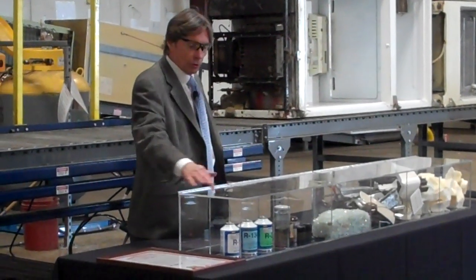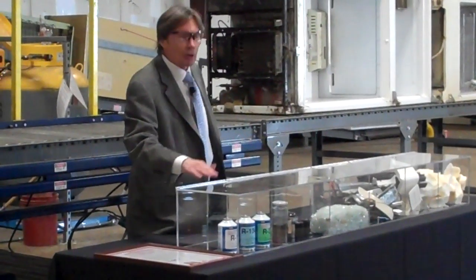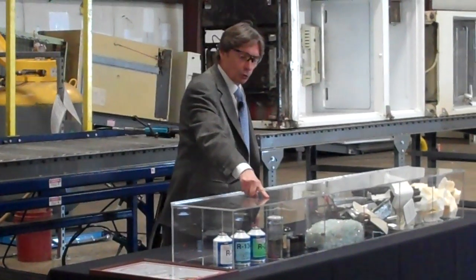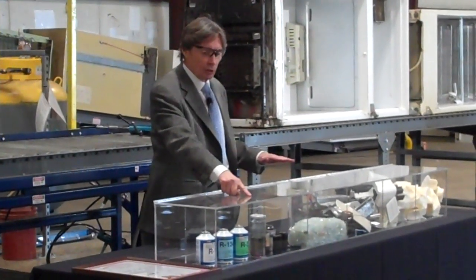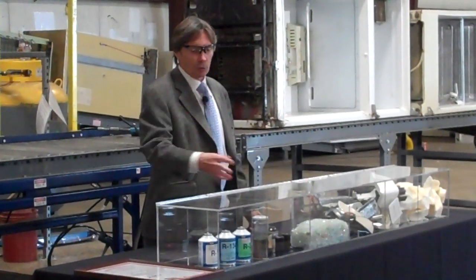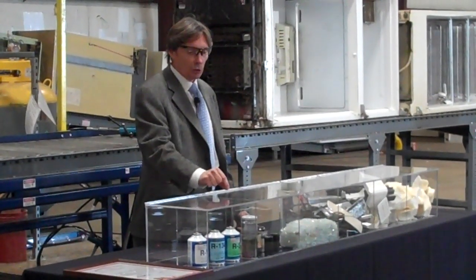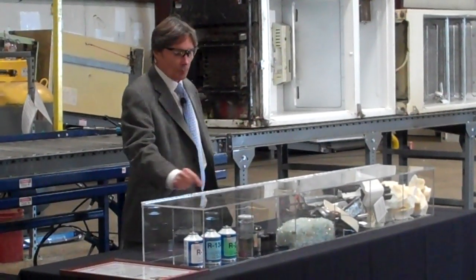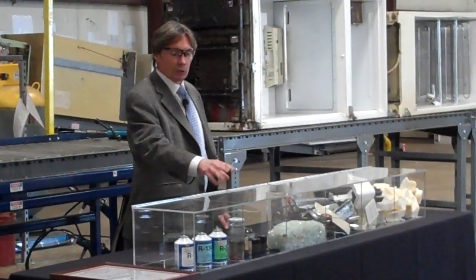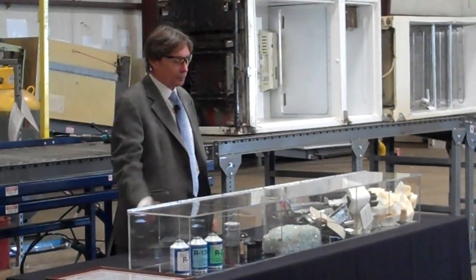The first one has what is typically known as Freon. They're refrigerants. You have CFC 12, HFC 134, and in air conditioners, which we do here too, we have 22. This one has compressor oil. When it resides in the compressor, it's actually a hazmat. What we do here is evacuate the refrigerant and the oil simultaneously and clean the oil so it can be reused as a clean mineral oil. We also have PCB capacitors and a mercury component there. We take those off. They are sent to a hazmat destruction facility to be destroyed.